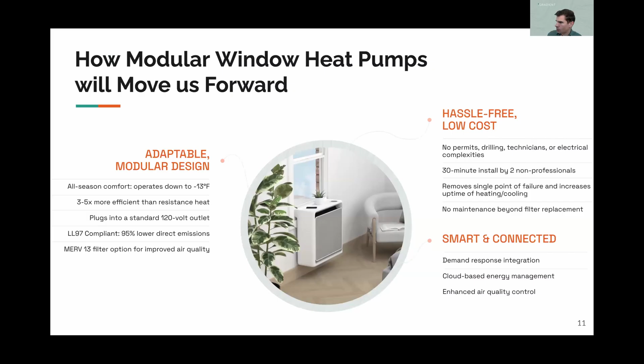So jumping back up, to summarize: we really want heat pumps to be very deployable and scalable. We want to control the quality of the install — we don't want the install process to go poorly because systems aren't matched, ducts aren't balanced, or refrigerant isn't charged properly. We want it fully packaged and deployable, so each install works like the last 100 installs. That's why a packaged window heat pump is better, and we believe it can deliver a significantly better in-home experience.